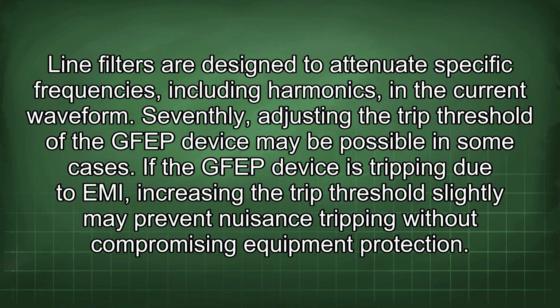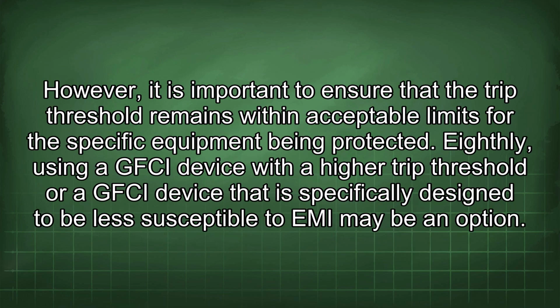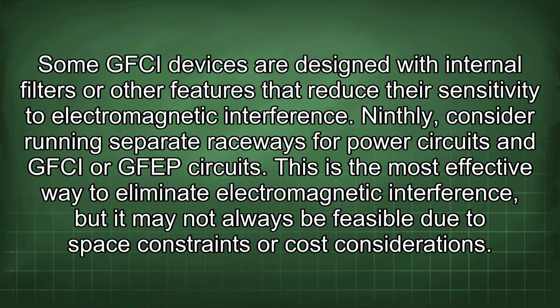Seventhly, adjusting the trip threshold of the GFEP device may be possible in some cases. If the GFEP device is tripping due to EMI, increasing the trip threshold slightly may prevent nuisance tripping without compromising equipment protection. However, it is important to ensure that the trip threshold remains within acceptable limits for the specific equipment being protected. Eighthly, using a GFCI device with a higher trip threshold or a GFCI device that is specifically designed to be less susceptible to EMI may be an option. Some GFCI devices are designed with internal filters or other features that reduce their sensitivity to electromagnetic interference.